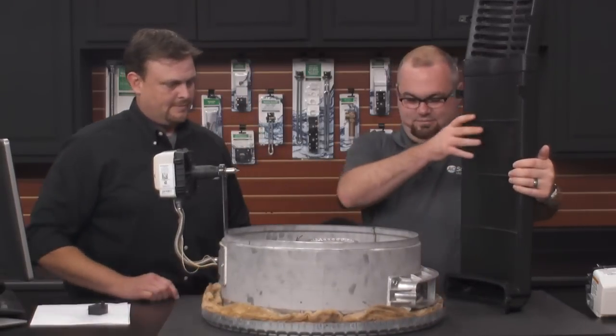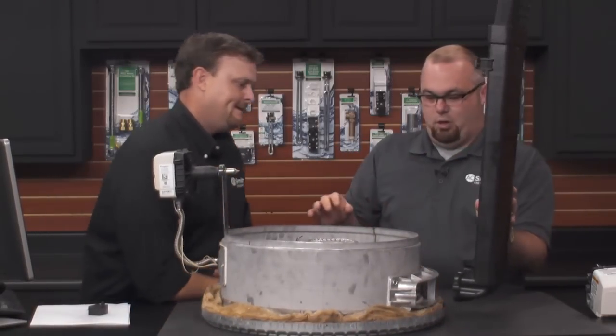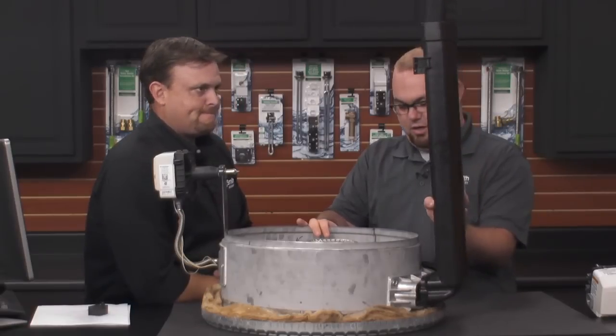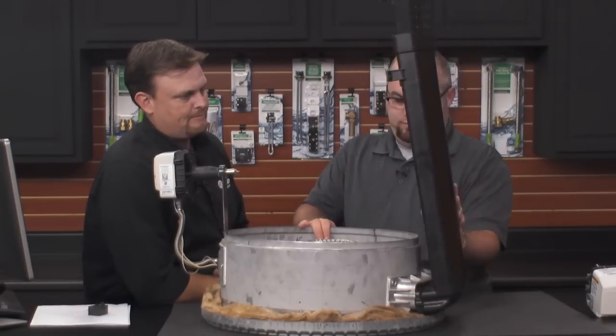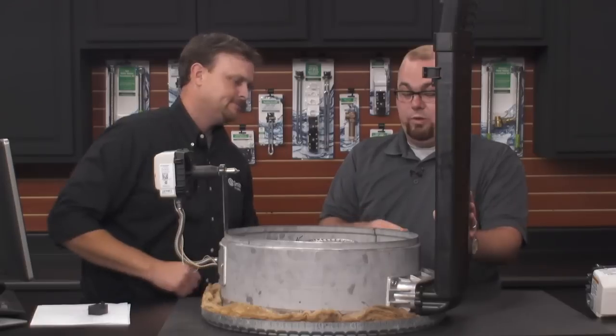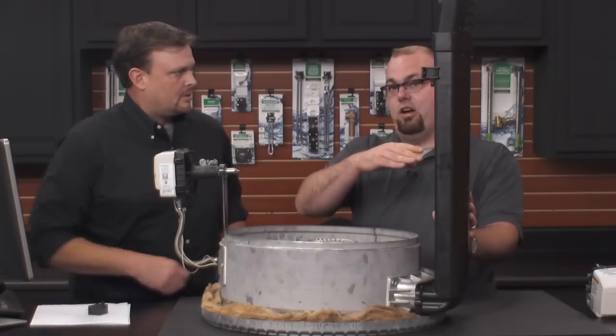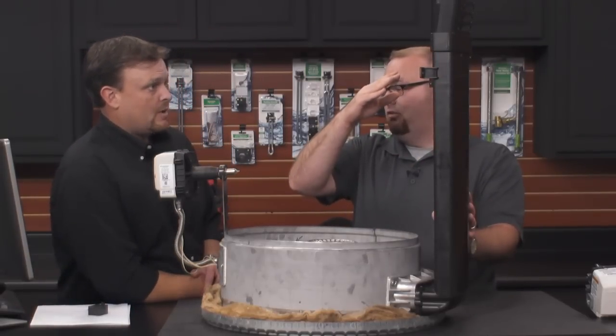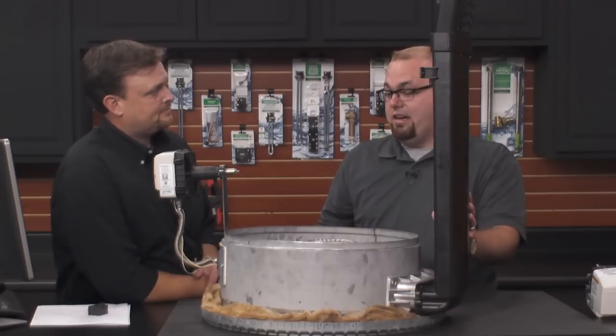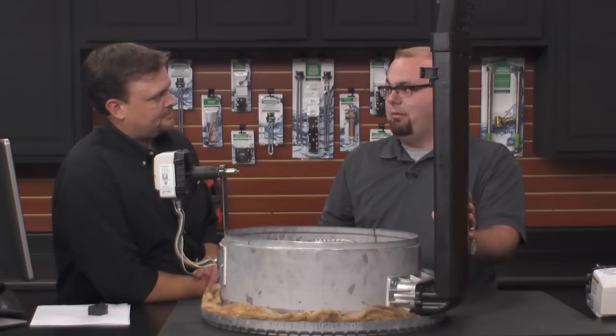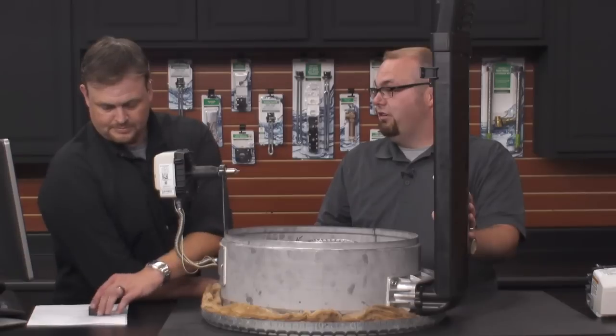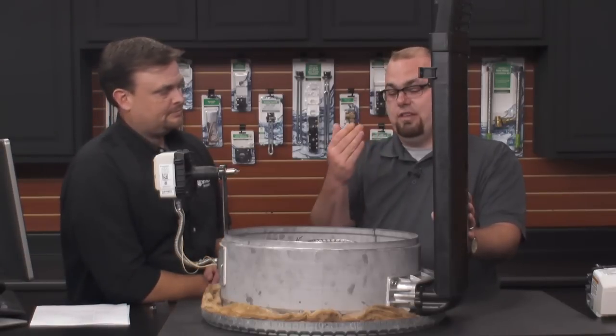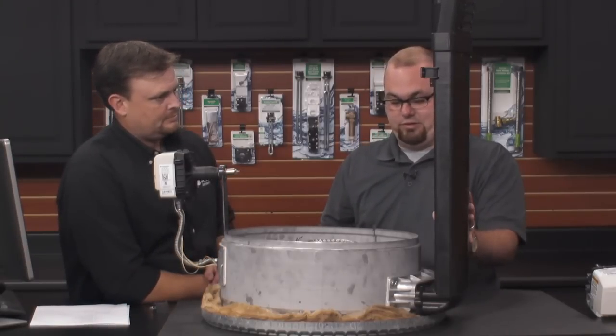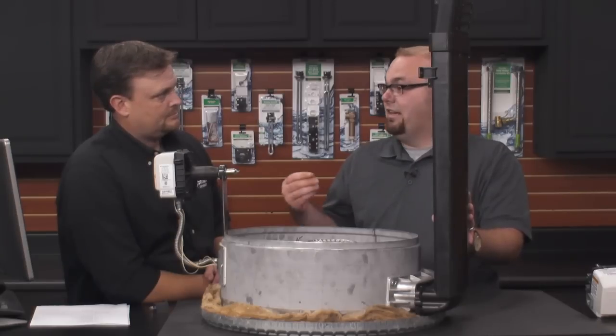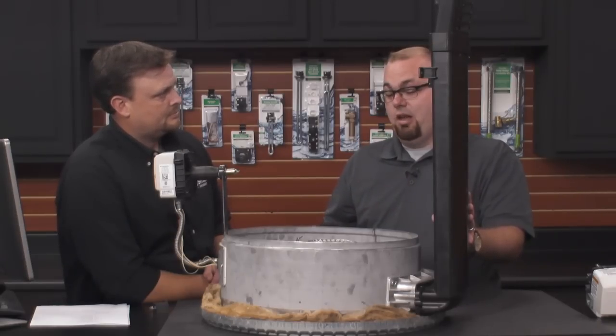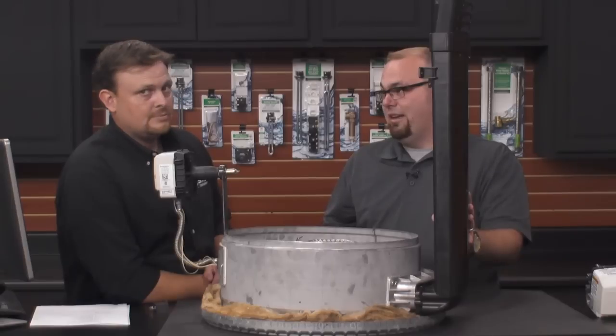Yeah. All right, and so this actually bolts to the back side of the combustion chamber right here, sort of like so. And when we do this, we're bringing our combustion air up several inches off the ground, right? And so if we do that, the heater actually doesn't have to have a flame arrestor, which is good because you have a lot less maintenance. So since we're using this, the heater does not have to have a flame arrestor, and so actually the heater is getting cleaner combustion air, but also it's less maintenance because you don't really have a filter you need to clean too much.